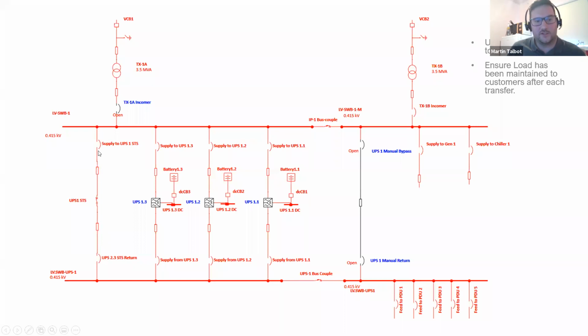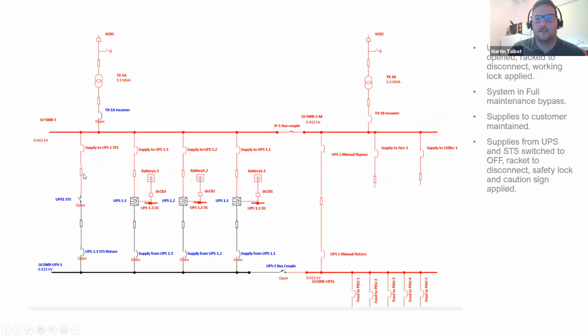Okay, so once we've transferred to the other side of the transformer via the bus coupler, we're going to close onto our static bypass supply. And this bypasses the inverters of the UPS. At all times we're ensuring that we've made good supply through to the customer at the bottom. Then we're going to close the manual bypass in parallel with the static, ensure they're in parallel, and then open the static bypass. And we've transferred our supply through to the manual bypass. We're then free to begin isolating this side of the board.